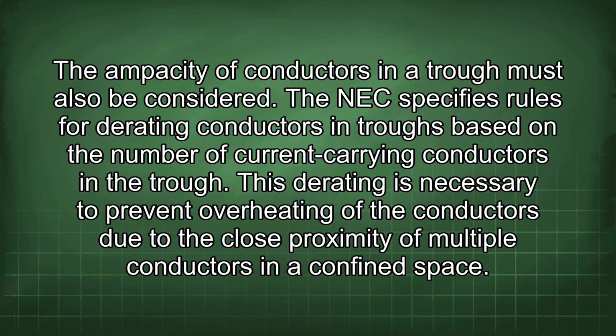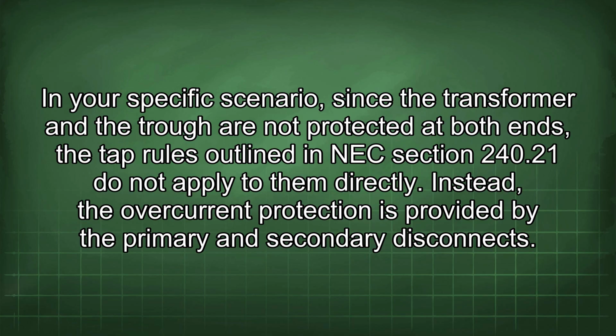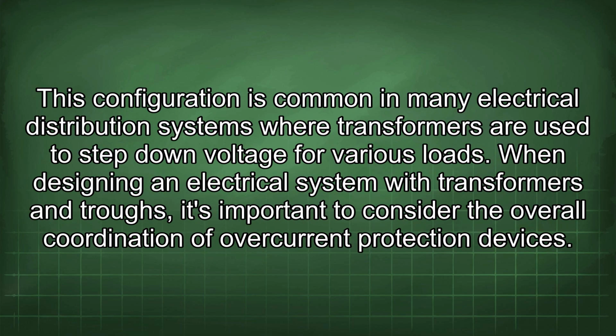In your specific scenario, since the transformer and the trough are not protected at both ends, the tap rules outlined in NEC section 240.21 do not apply to them directly. Instead, the overcurrent protection is provided by the primary and secondary disconnects. This configuration is common in many electrical distribution systems where transformers are used to step down voltage for various loads.